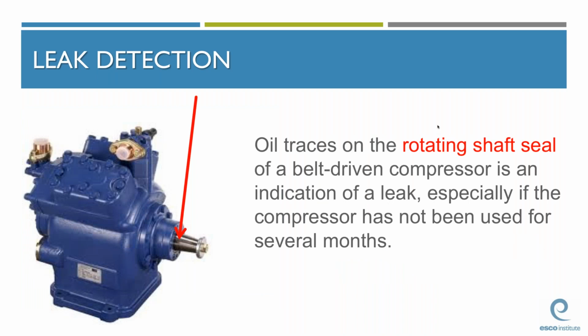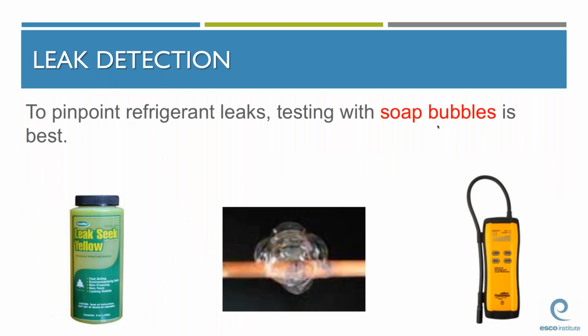For example, the rotating shaft seal on an open or belt-driven compressor tends to leak if the compressor has not been used for an extended period of time. So traces of oil on this seal indicate that a refrigerant leak is likely. Of course, soap bubbles are a very efficient way to pinpoint leaks, and as instructors, we all know that this method is the least expensive, making it a really popular choice for use in our training program.